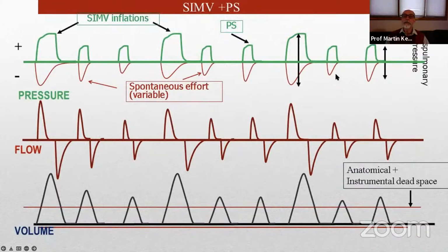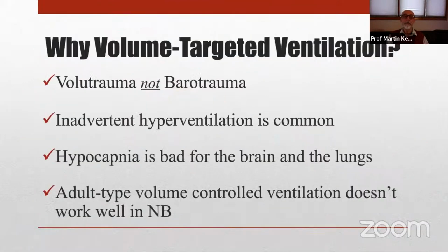6 may be a reasonable starting point, but then you have to look at what tidal volume you're achieving with that pressure support, and if it's still not at least 3.5 to 4 ml per kilo, then you need to increase your pressure support. Of course, I have for a number of years advocated volume-targeted ventilation as an important lung protective strategy. And I will show you some evidence that it's excessive tidal volume rather than pressure that matters most in terms of lung injury.